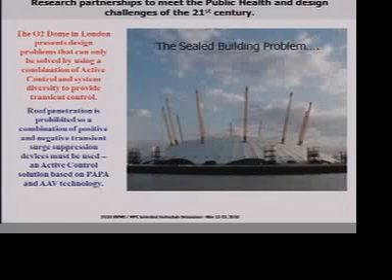Now we have a possibility to actually control transients. For a very long time, we've had air admittance valves that control negative transients. The PAPA allows us to control positive transients. Therefore, we can address the problem of the sealed building.